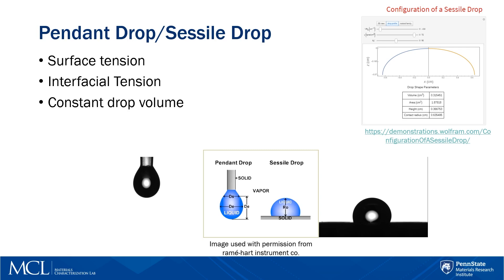But what happens when we don't know the surface tension values of the liquids used for the measurements? In this case, we can use a technique called pendant drop and sessile drop to gain more information about the surface tension. Both methods analyze the shape of the drop, either as it hangs from the syringe tip or as it sits on a solid surface. On the bottom of the screen is a diagram paired with the actual images from our instrument. We have the ability to feed back off of the volume calculated in the live image to keep a constant drop volume.